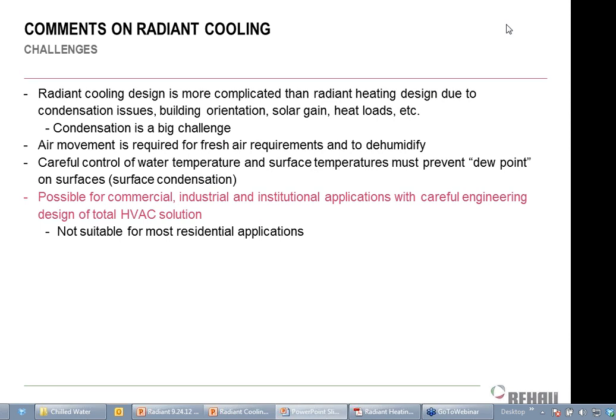This is appropriate for some commercial buildings and not others. Obviously, any buildings where you're going to be opening doors and leaving them open for a long time wouldn't be good, like a warehouse, for example, or that car dealership we mentioned earlier. So the places where radiant heating thrives tend to be a little bit scarier for radiant cooling, because I don't want any outside air coming into my space and causing me to hit the dew point. But other places like schools, universities, libraries, things like that, radiant cooling can be done quite nicely.